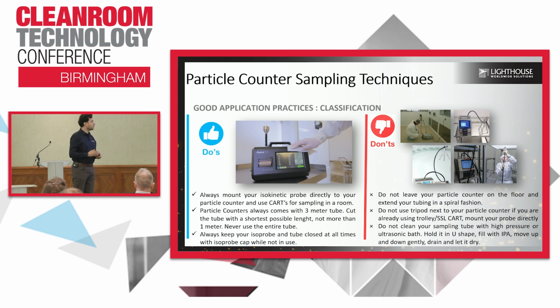And always keep your isoprobe and the tube closed at all times to protect your particle counter from the ambient particle conditions, because we do not always put these particle counters within the clean room. So if they are in the qualification department, for example, don't leave them with the open hose because it will also affect the particle counter. One of the things that I can add: always do the zero count check before starting the measurement, because it is important to see right at the beginning whether your particle counter is counting the real particles or having a technical issue.